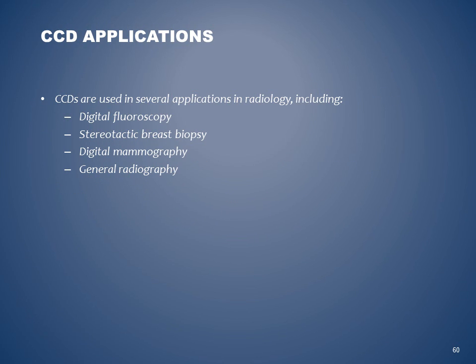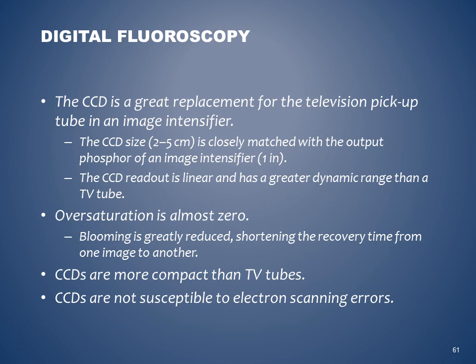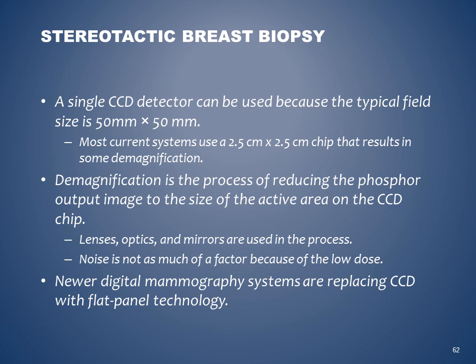CCDs are used in several applications in radiography, including digital fluoroscopy, stereotactic breast biopsy, digital mammography, and general radiography. Digital fluoroscopy: the CCD is a great replacement for the television pickup tube in an image intensifier. The CCD size, 2 to 5 centimeters, is closely matched with the output phosphor of an image intensifier, 1 inch. The CCD readout is linear and has a greater dynamic range than a TV tube. Oversaturation is almost zero. Blooming is greatly reduced, shortening the recovery time from one image to another. CCDs are more compact than TV tubes. CCDs are not susceptible to electronic scanning errors.